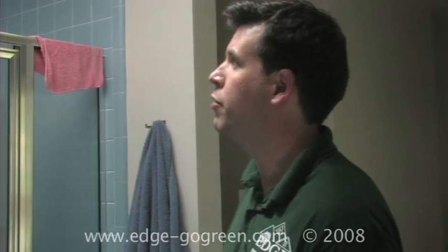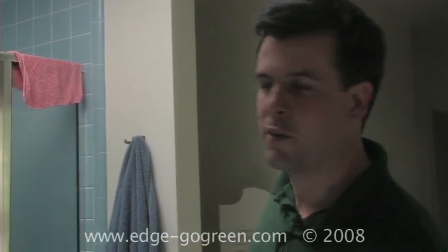And that warm, humid air over time will do one of two things. One, it'll decay building materials, so it'll decay framing and drywall, but more importantly, it will drive paint failures. And you can see up in the skylight shaft, we've got peeling paint on both sides. So what we've done, instead of moving the skylight shaft, which is expensive, is to install a bathroom fan in one of the side walls of the skylight shaft itself, which is now controlled from our motion sensor switch. This is going to, every time they use the shower or even enter into the bathroom, turn this fan on, which will remove moisture and any other stale air that's inside the bathroom.